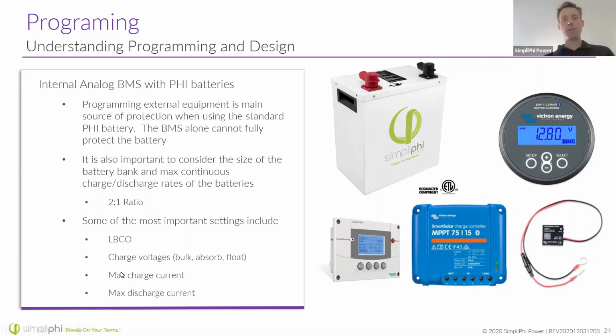You want to make sure that you program in the max current, right? And it's 37.5 amps per battery for the Phis. And the max discharge current is the same, right? So it's per battery. So if you have 10 batteries, you could get 375 amps out of your bank.